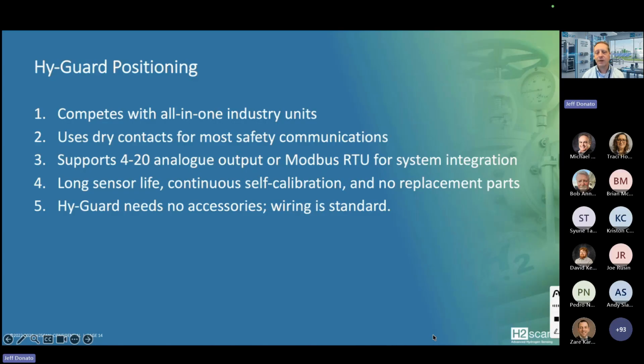As Sue stated, with the WAGO connectors that are on the unit, basically you just pull the tab up, insert your wire, and push down. There's another style where you push down on a button and insert your wire, but really no special tools, no special cables required for this. There is a wiring spec in the manual, and you can reference that to see which wires you need to purchase from any electrical supply house to install the HY-GUARD.